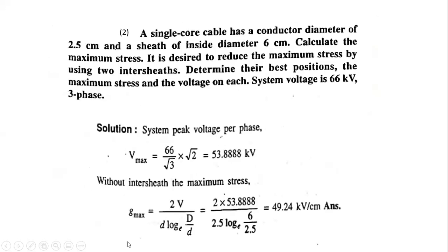This is the problem related to the grading of the cable. Basically there are two types of grading: capacitance grading and intersheath grading. Why do we grade the cable? To uniformly distribute the maximum dielectric stress in the cable.